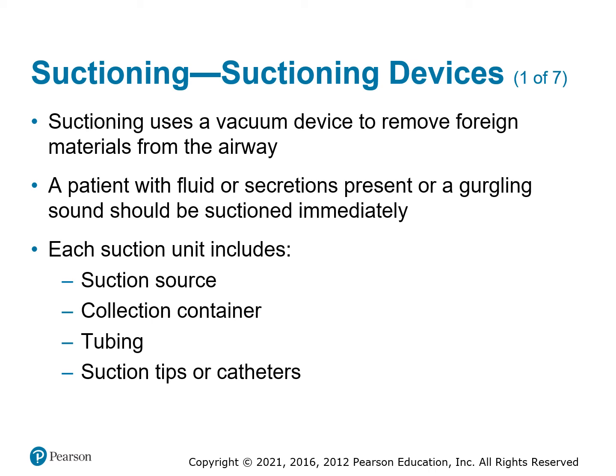Suction devices, we have manual, we have battery powered. There are oxygen powered suction devices, and then the ones in the ambulance are powered by a compressor. So know what systems you have, how each one of them works, and then the important thing, test it before you start your shift. Test it throughout the shift to make sure everything's good.